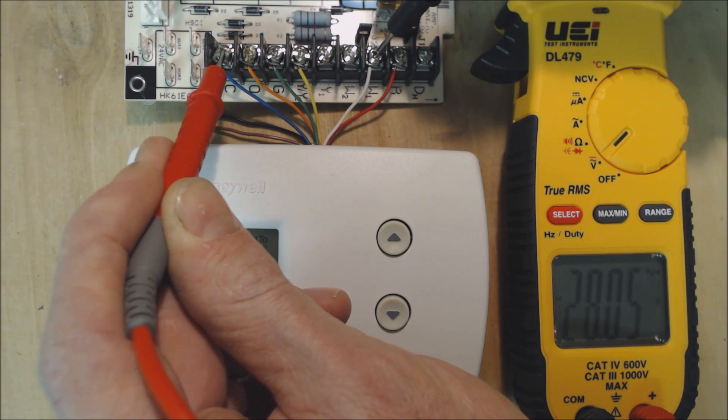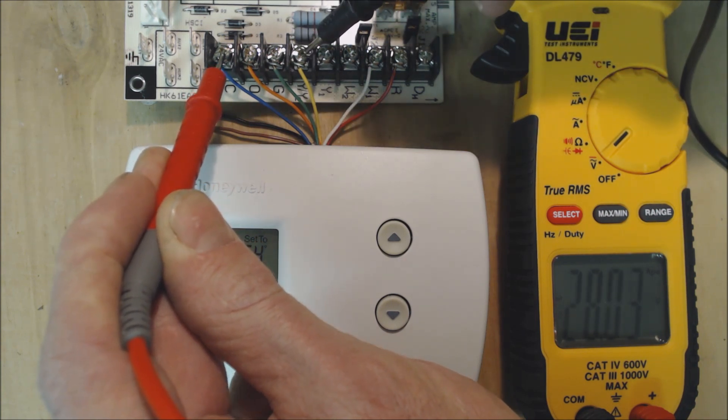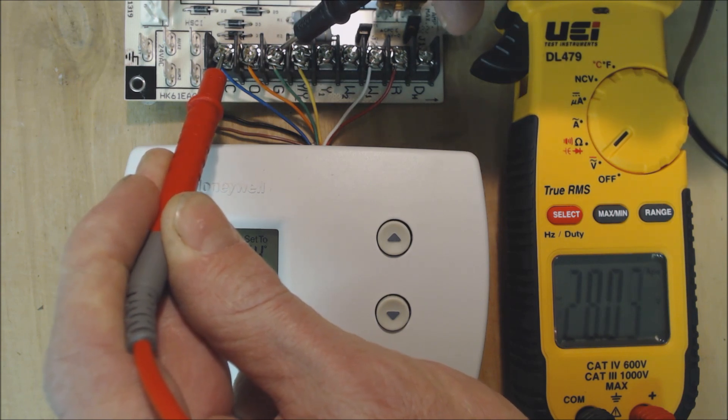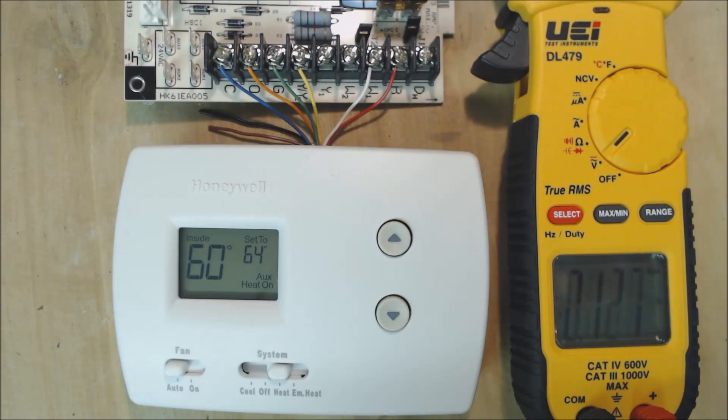We're going to read that now. 28 volts for W, and we still have our 28 volts on Y, we still have 28 volts on G, and we do not have any voltage on O, which is correct. In this case, that auxiliary heat could be electric resistance, it could be a hot water coil, something along those lines.